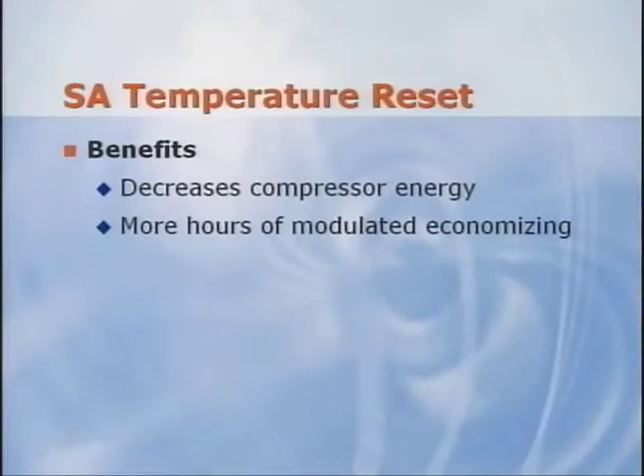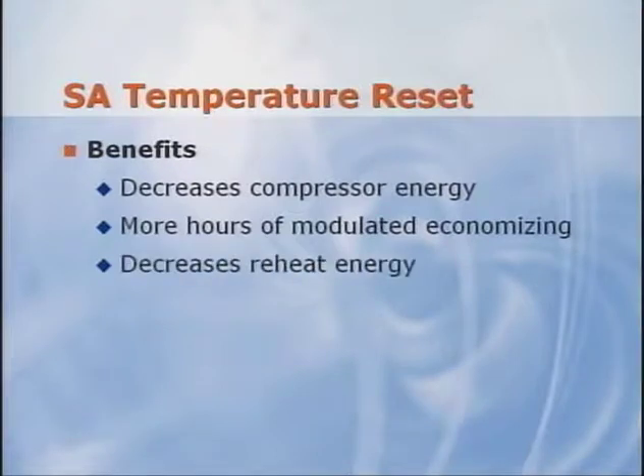In a VAV system, it's tempting to raise the supply air temperature at part load conditions in an attempt to save energy. But it's important to understand the trade-offs of this strategy. Increasing the supply air temperature can reduce compressor energy and increases the benefit of an air side economizer. For those zones with very low cooling loads, where supply airflow has been reduced to the minimum setting of the VAV box, raising the supply air temperature also decreases the use of reheat energy.